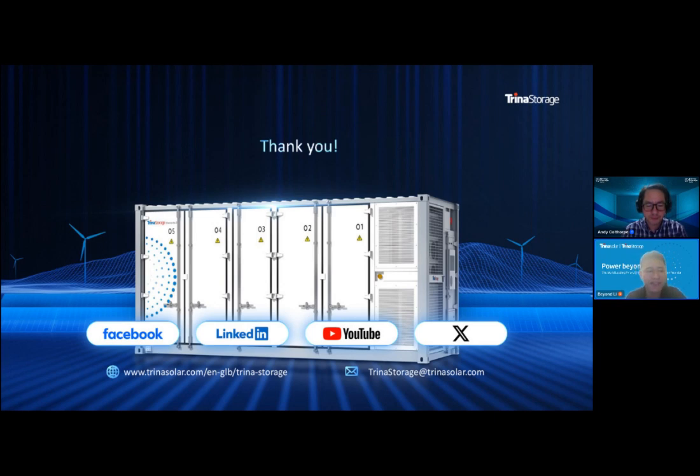First, by having even larger battery cells, you can integrate, from our side, an even larger energy capacity of the battery systems. As of now, what we have is a 5 megawatt hour unit. So by having an even larger battery cell capacity format, we can build up even a 6 or 7 megawatt hour per 20 feet container. This could be amazing when it comes to cost reductions by, for one thing, the curtailment of the relevant auxiliary parts and components that were generally fitted for the battery modules. With fewer modules, the components will be fewer accordingly.